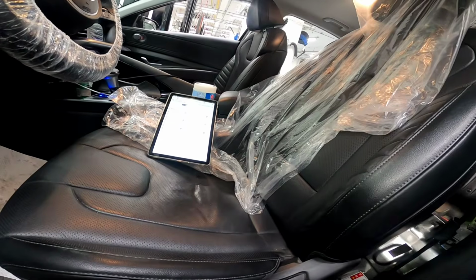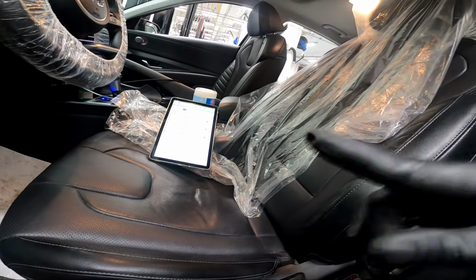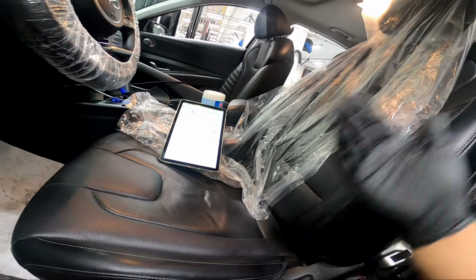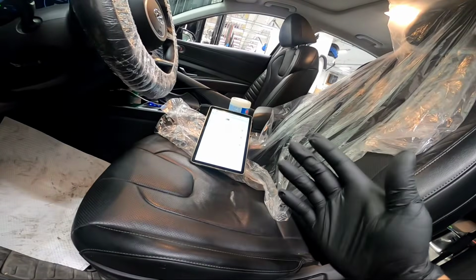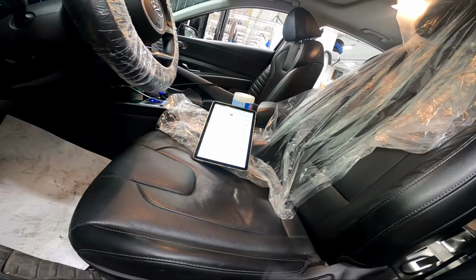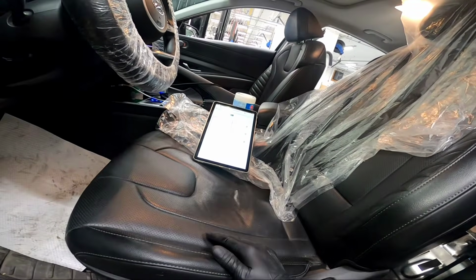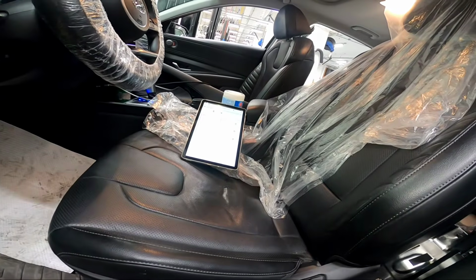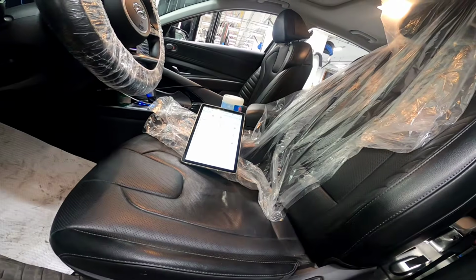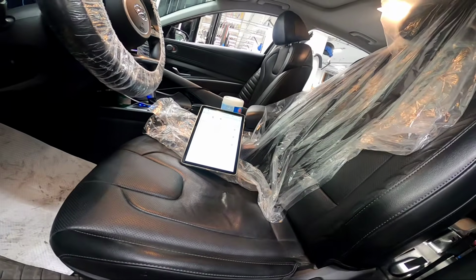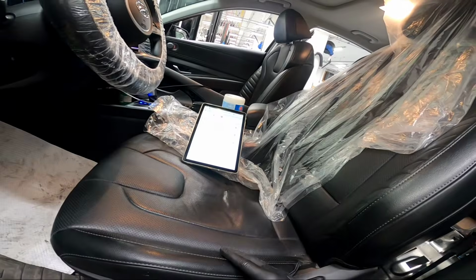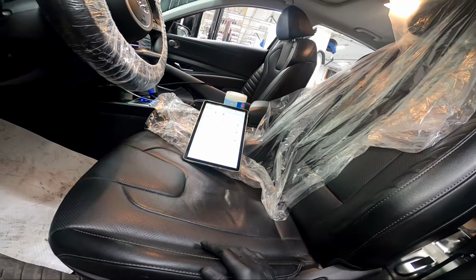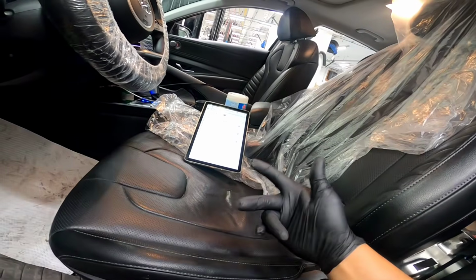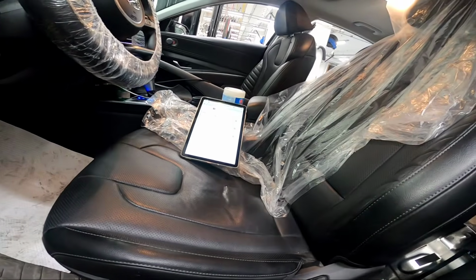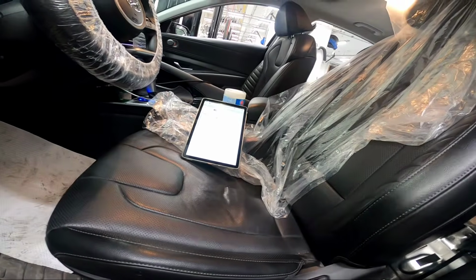how did I end this video? But anyway, the relay on the old one, the switch side was stuck closed. That's why there's still power going out when we did our shut-off procedure. Maybe during our diagnosis, if I did that, I would have known, right? But I just jumped the gun, we got a relay fault, and I wanted to check right away straight to our power relay and see if the relay is working normally. But in that case, we thought there was an open circuit on the coil. That's why we just, you know, that's it, because there's no point if the coil is open. There's no point really to go further, because you need that coil to be working so that the switch can turn on. Anyway, yeah, that's a good lesson learned for us.